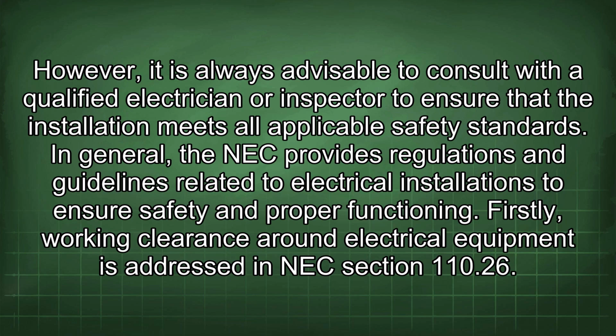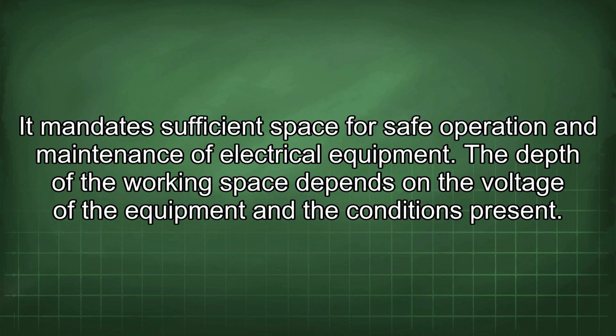applicable safety standards. In general, the NEC provides regulations and guidelines related to electrical installations to ensure safety and proper functioning. Firstly, working clearance around electrical equipment is addressed in NEC Section 110.26. It mandates sufficient space for safe operation and maintenance of electrical equipment. The depth of the working space depends on the voltage of the equipment and the conditions present.